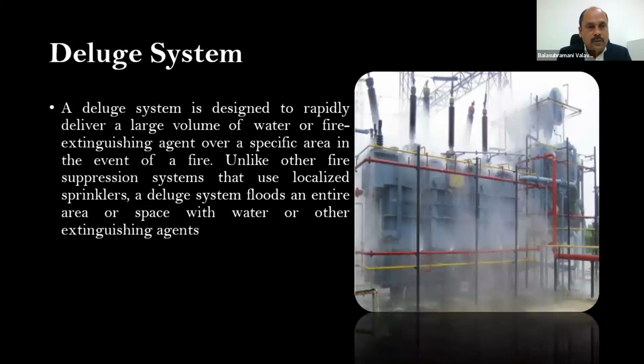The next system is the deluge system. It's basically used to extinguish the fire by pouring a large volume of water, especially in the transformer area, where the amount of water required is more, and when a fire happens, you cannot take any chance at the particular place. You have to pour the water on the entire surface. The overall volume of the transformer shall be covered by applying the water on the entire surfaces. It will suppress the fire.